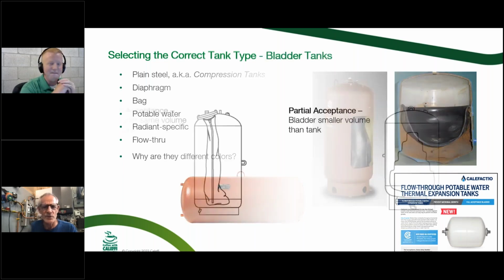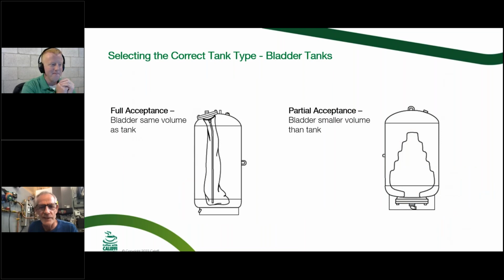Now one of the other questions, Cody, and I don't know if I put a slide in for it, but if I did, sorry, it's going to come up again. Somebody said, when do I have to go to an ASME tank? I can't find an exact answer for that, even from the people that make the tanks. So I searched around a little bit. In some places, your state inspector, it could be a boiler code that's going to supersede the mechanical code. I did find online that Michigan and Ohio have 3 criteria. They say if it's over 210 degrees temperature, if it's over 200,000 BTU input, and if the tank is larger than 120 gallons, that's their 3 criteria for when you have to go to an ASME tank. And I don't know if that comes out of the boiler code or if that's just something they're comfortable with.